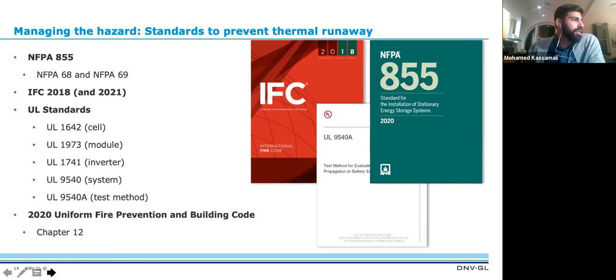Managing the hazard and protecting against thermal runaway, which is the hazard we defined earlier, can be done in many ways. This starts off as a construction assessment: you want to understand that these components are fit for purpose. Do they have the certifications we just mentioned, UL 1973, UL 1741, et cetera? But also do the smaller components, such as nuts and bolts, fit properly for the solution, and are they properly suited for outdoor use, et cetera?